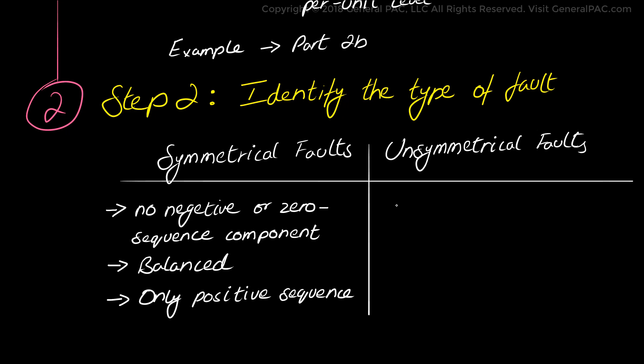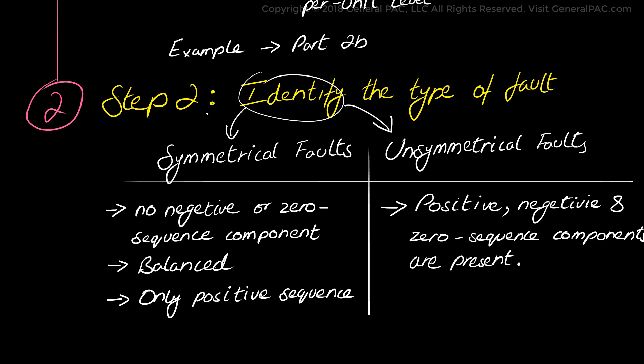And on the other hand, there are unsymmetrical faults that mandate the calculation of positive, negative and zero sequence components separately. And because of these different types of faults that occur in power systems and their different characteristics, we really have to identify the type of fault that is being analyzed. Because the remaining steps are dependent on it.